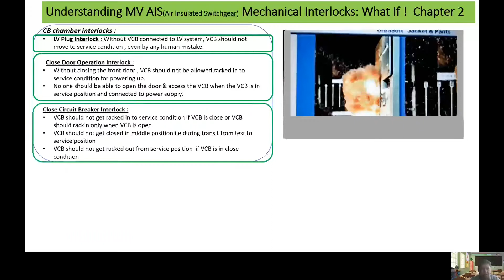Next, we are going to talk about the closed circuit breaker interlock. To understand this interlock, we have to first understand two contacts. The one contact is the vacuum interrupter contact, which is chopping the current, or you can say closing the circuit breaker, opening the circuit breaker, and extinguishing the arc in a vacuum environment. So this is part of the circuit breaker closing and opening operation.